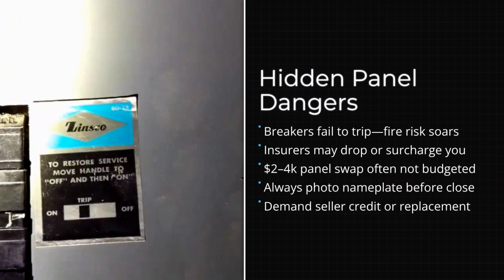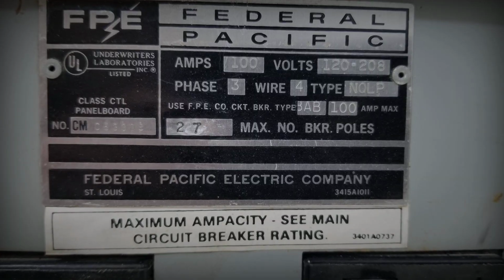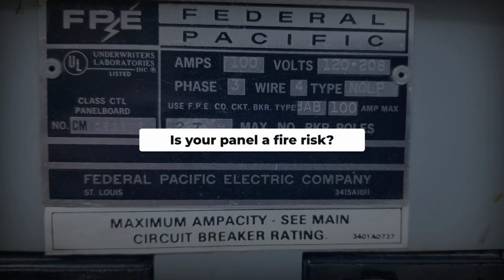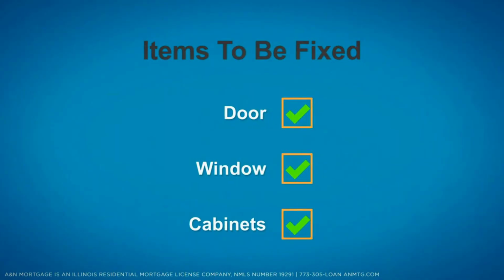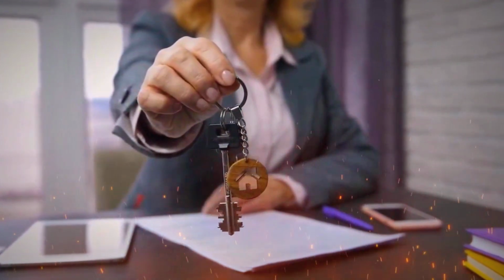Buyers should demand a clear photo of the panel nameplate and a written statement from the seller. Is the main service panel Federal Pacific or Zinsco? If it is, negotiate a replacement or repair credit before closing. Once the deal's done, the risk and the bill become yours.